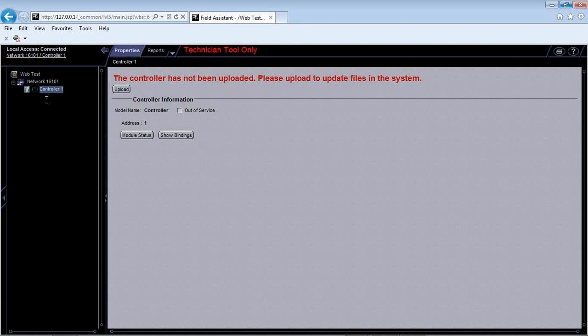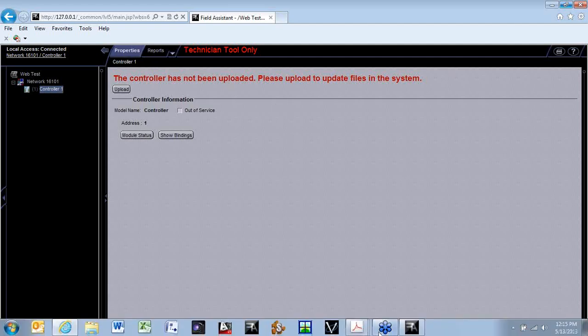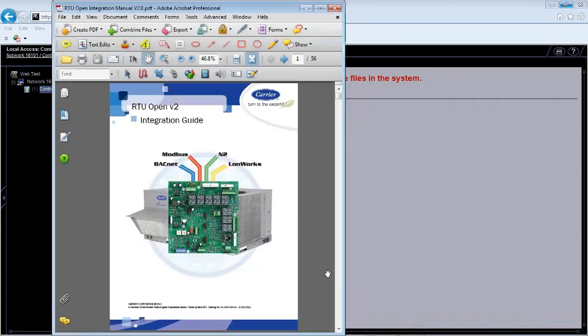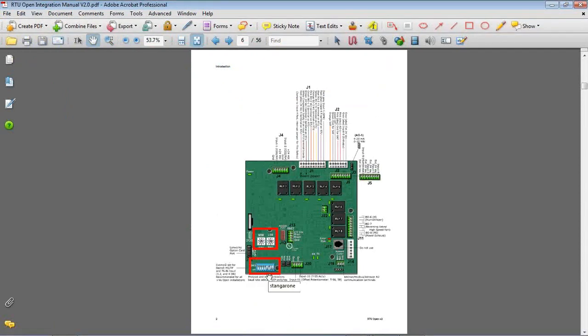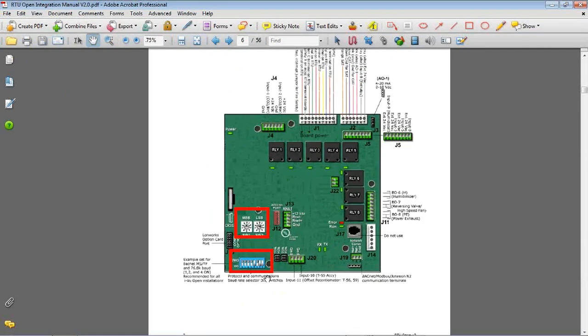Now you can see on the left hand side here we have this tree and it's going to show you controller 1. This is the controller that I'm locally plugged into. If I had more than one controller wired together on my communication bus, there would be more controllers showing up on this network. And this number 1 is actually the local address on that controller. So if I go back to my installation manual, or actually my integration manual, and look at the Rooftop controller, scroll down a couple pages here, depending on how familiar you guys are with communication systems and controls, each controller has to have a baud rate and an address.